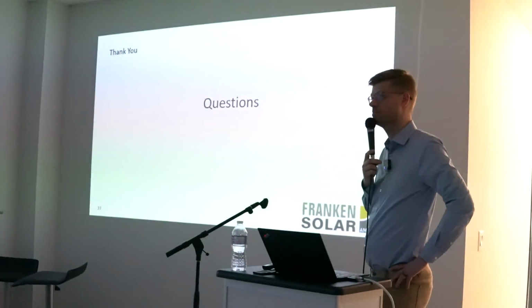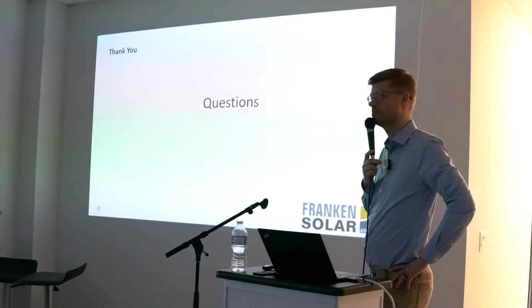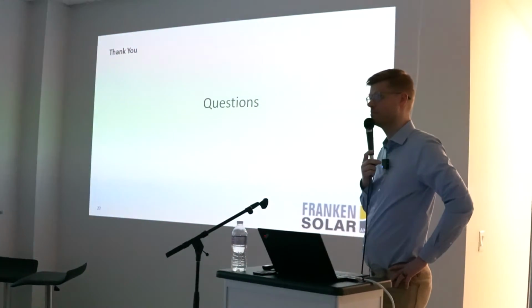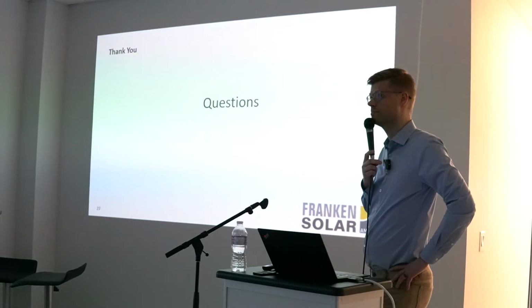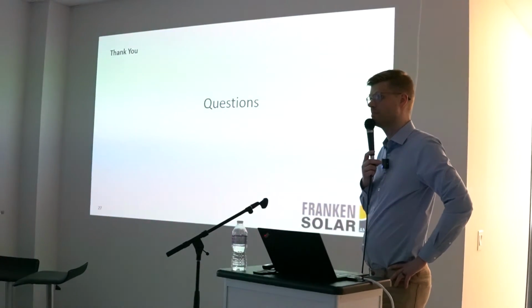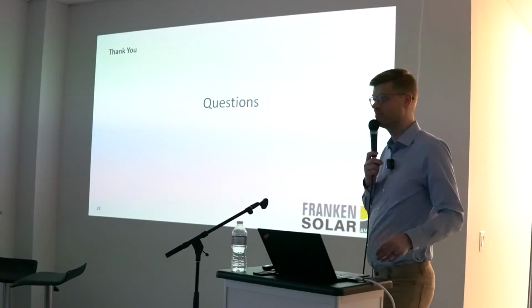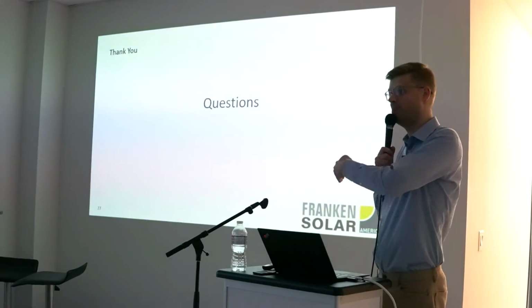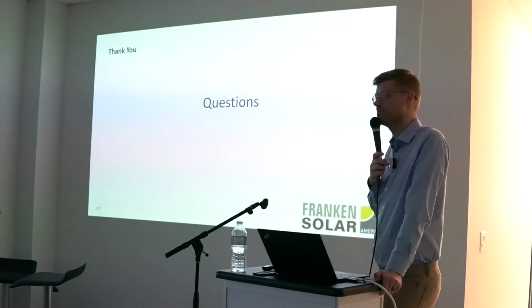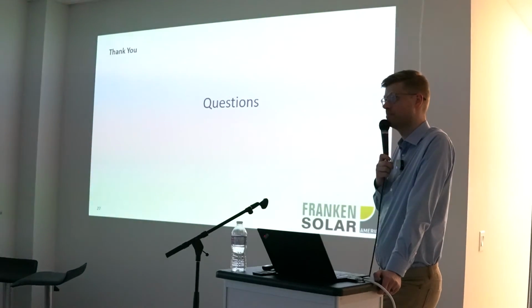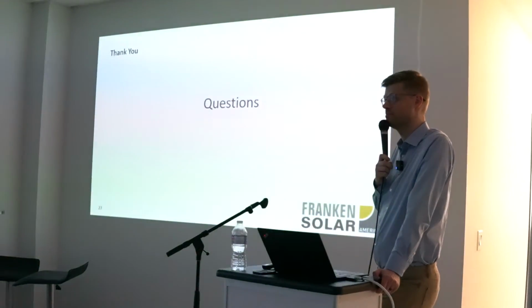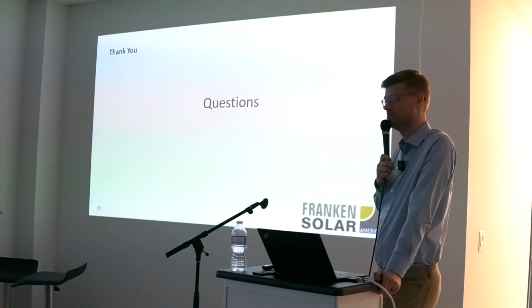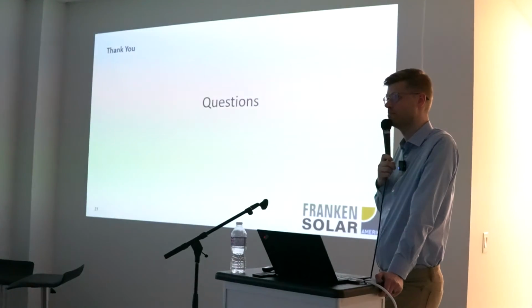in terms of the separation distances, as per manufacturer's recommendation, yes, it is acceptable based on the UL9540A test, but ultimately one has to live with this equipment for the next 20 years. And this is where the insurance companies come in. They might have their own guidelines. So not might, they have their own guidelines. Typically it's based on the NFPA in the US. It is even more stringent than the recommendations from the manufacturers. So if one is looking at an energy storage project, the first thing is to refer to your insurance company as to what their recommendations are in terms of separation distance.